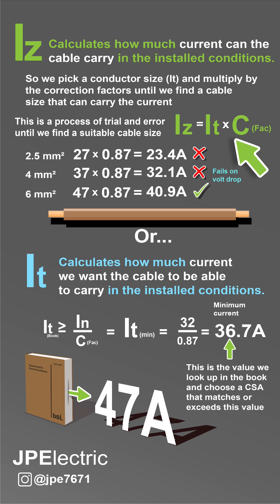This is a process of trial and error. It turns out that 6mm² cable with a current carrying capacity from the book of 47 amps is suitable. The current carrying capacity as installed in these conditions for this 47 amp cable will be 40.9 amps. It can be quite involved calculating your current this way because it is trial and error.